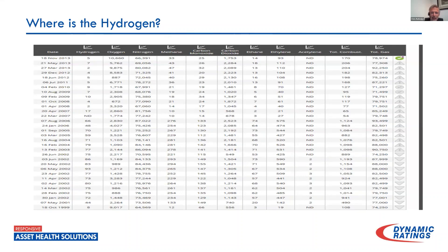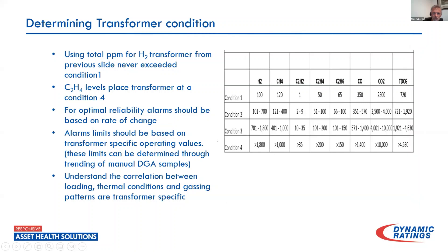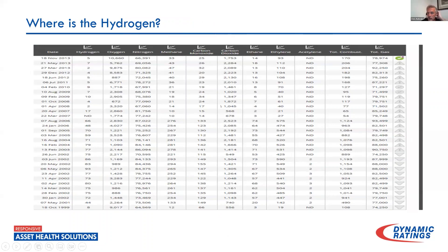This was where I really started looking at carbon oxide ratios — I've got several papers floating around on that. The way the ratio was acting really led me to believe I didn't have a lot of solid insulation being affected — my paper wasn't being affected by whatever was going on. It turned out to be a connection issue that was just overheating — something that needed to be addressed but not necessarily a failure of the transformer. In fact, this transformer is still in service today.